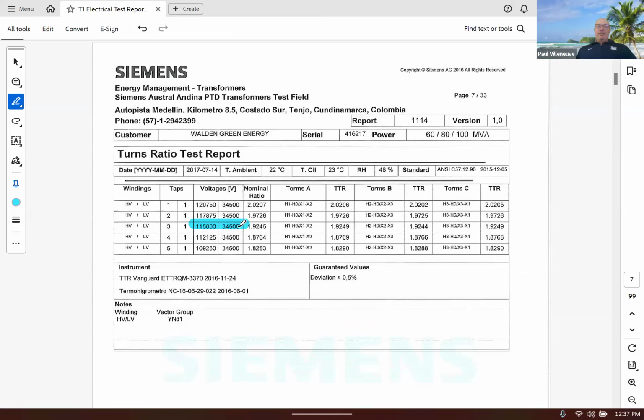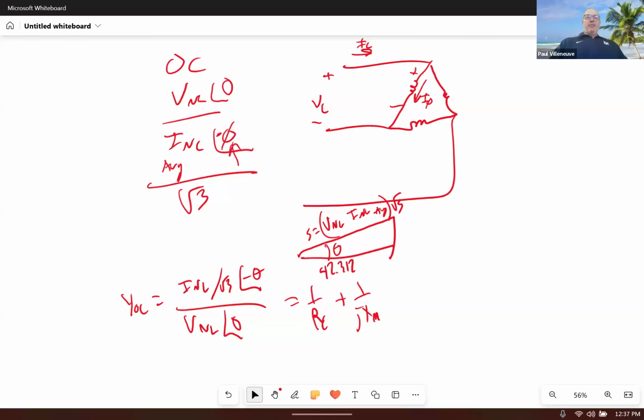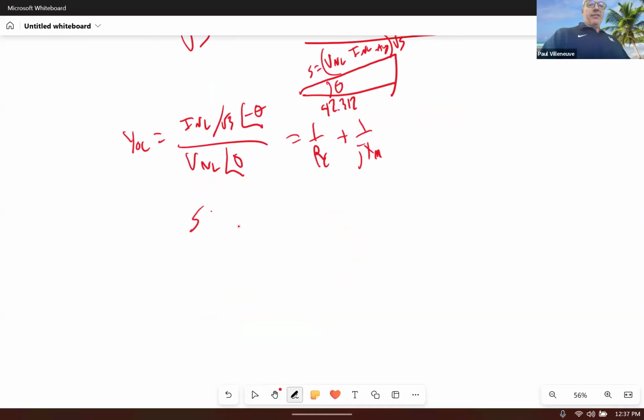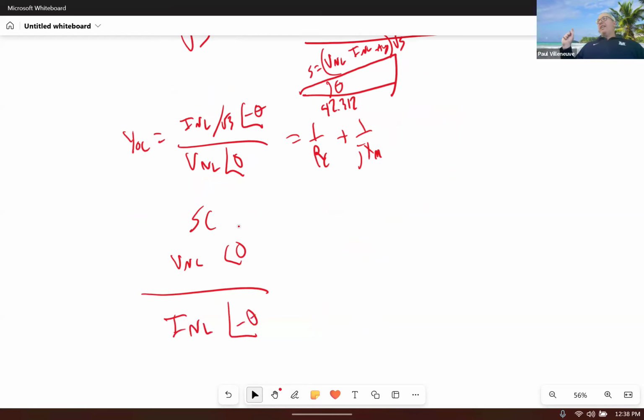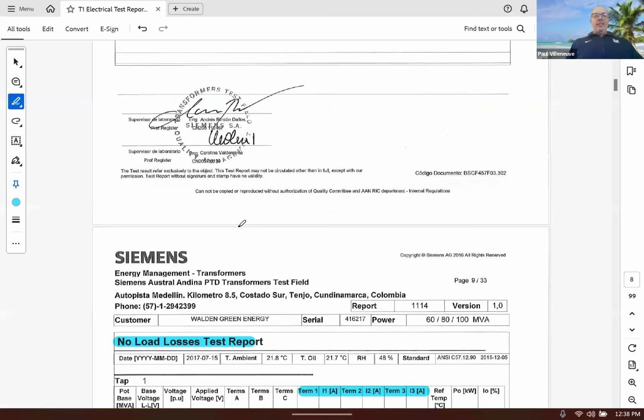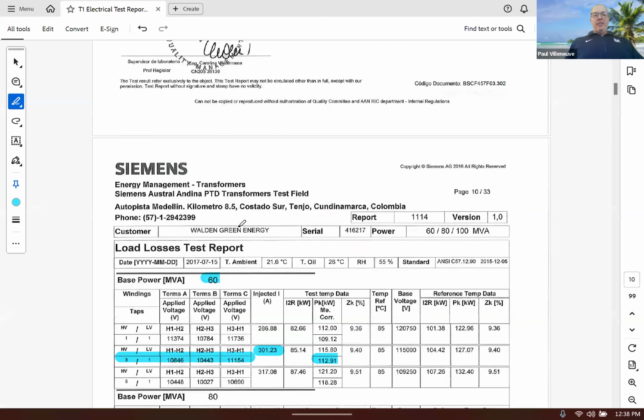Okay. So now I'm going to do my short circuit test, which I've got my V no load, which is at an angle of 0, divided by my I no load, which is at an angle of theta. This is a Y connected winding, right? Because this is on the 115 kV side. How do I know it's 115 kV? It tells me. It tells me it's on H1 to H2. That's where the test was applied, which was the high voltage winding we saw at the beginning, on page 2 of the report. So this is the high voltage winding.